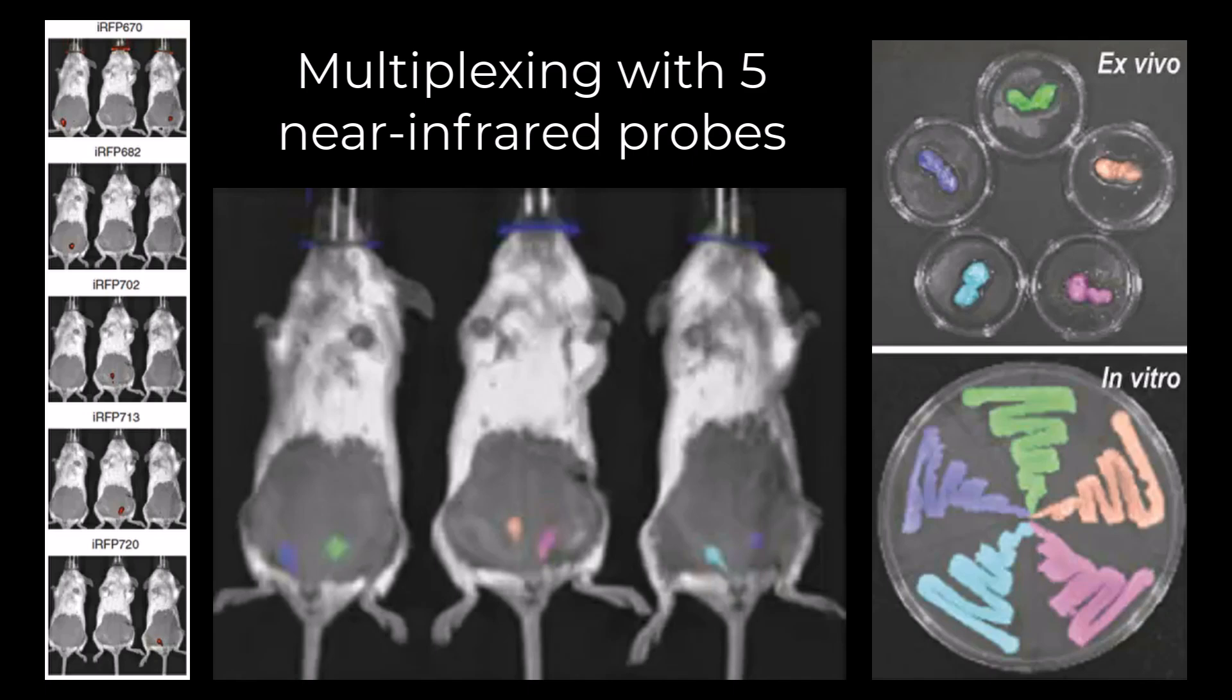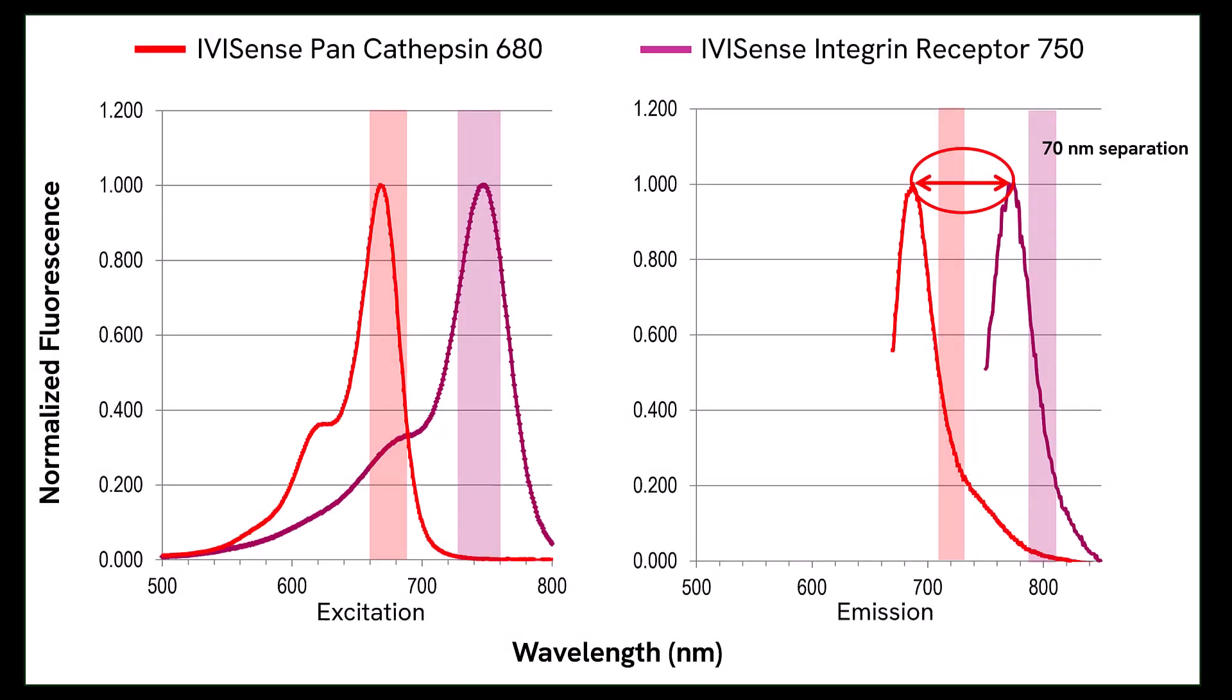Lastly, spectral unmixing can help resolve signal from probes with overlapping excitation and emission curves. Spectral unmixing can accurately determine and separate the percentage of a pixel's intensity into spectral components, allowing for accurate quantitation and multiplexing even into the near-infrared. Even small shifts can be detected, as shown here where five near-infrared probes were separated and independently displayed.